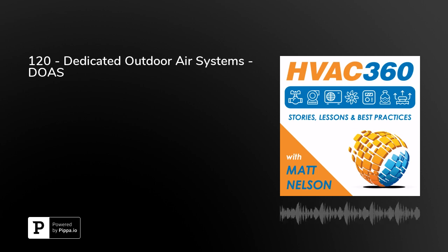So a DOAS unit is typically not just used alone. It is typically part of a bigger system, married together, that acts as a complete solution for a building. Like I said before, this one handles the ventilation, and then you have a component of your system that handles more of the internal loads. It'll handle enclosure loads, and it'll handle the people sensible loads.